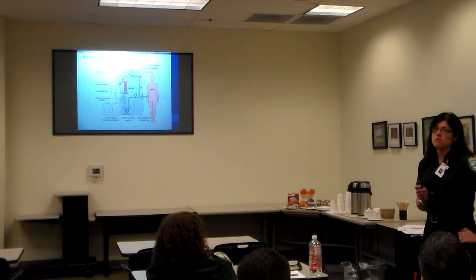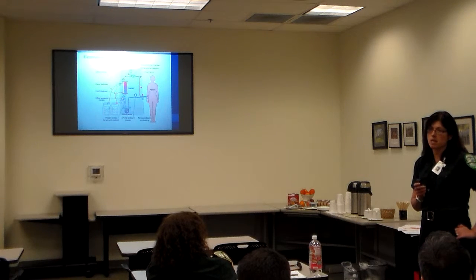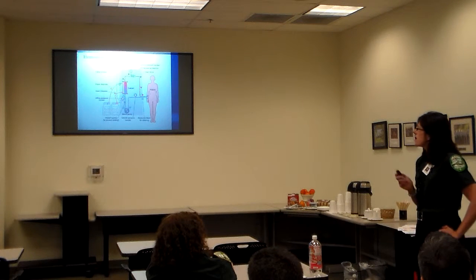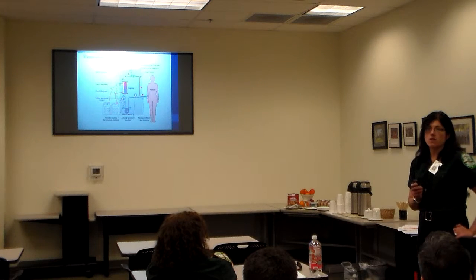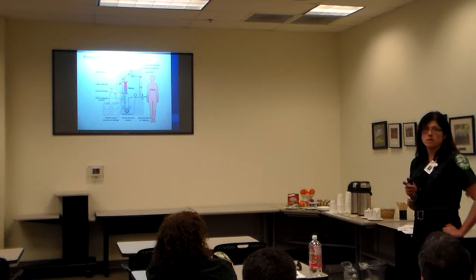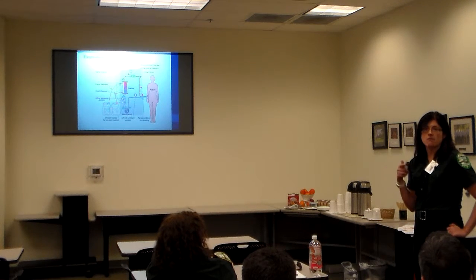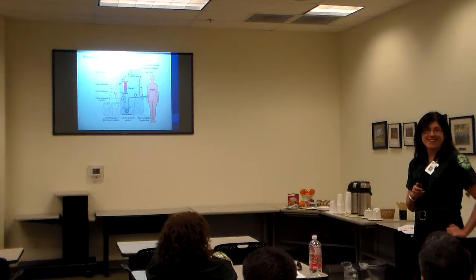The dialysis flow runs on average between a minimum of 600 mils a minute to 800 mils a minute. Those dialysis machines get switched on when the tech comes in. Definitely by 3:30, you have 15 machines up and running. We put them in minimal flows at that point at 500 mils a minute. Those dialysis machines don't get switched off until about 6 o'clock at night. So you're constantly running. So I'll let you do the math on that. It's a lot. It's a heck of a lot.